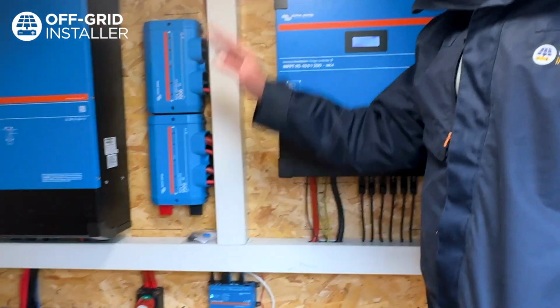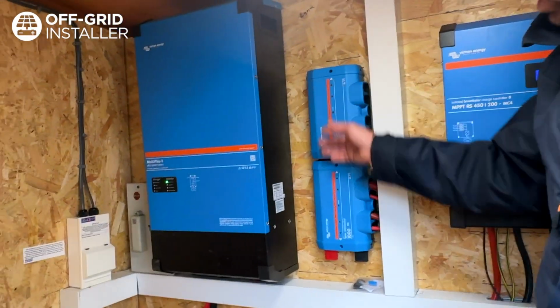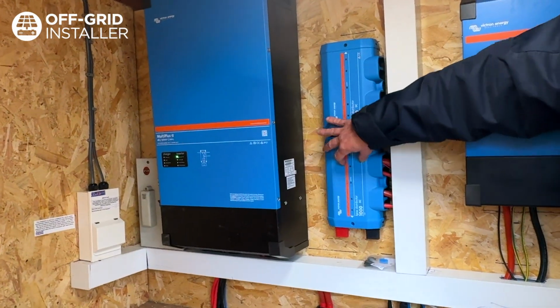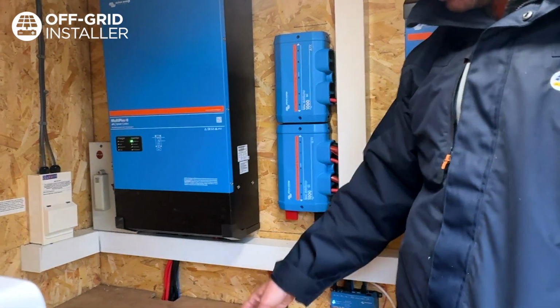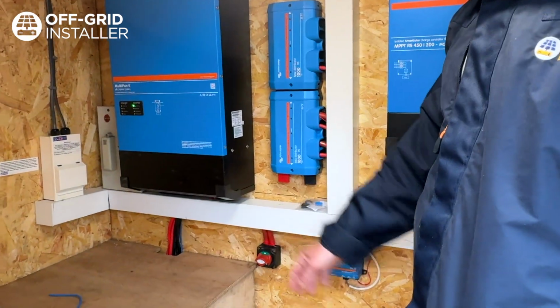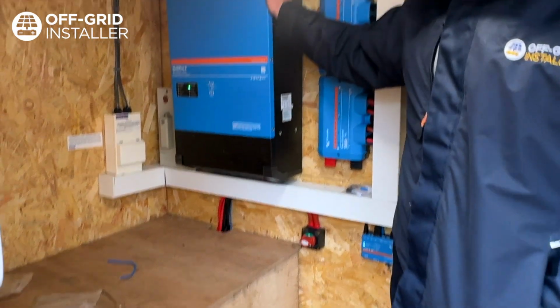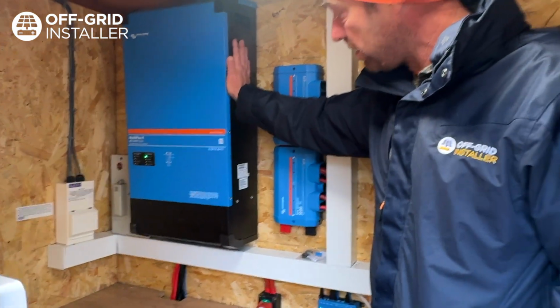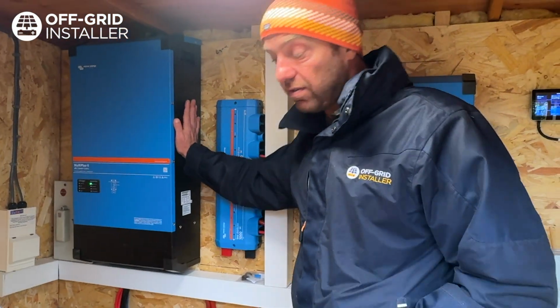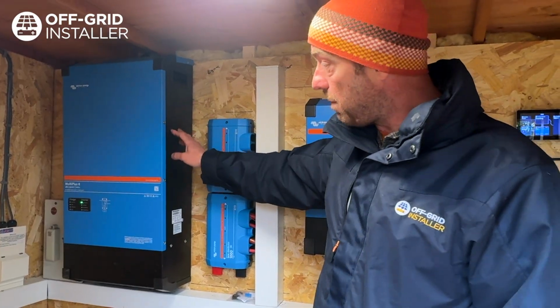You've got the trunking, hiding all the cables. Here, your Lynx Distributors with mega fuses. So this is fused, that's fused, and every 2 batteries in the box here are fused. This is a 15 kVA Multi Plus 2 Victron, so this will give you 12,000 watts of continuous power output.